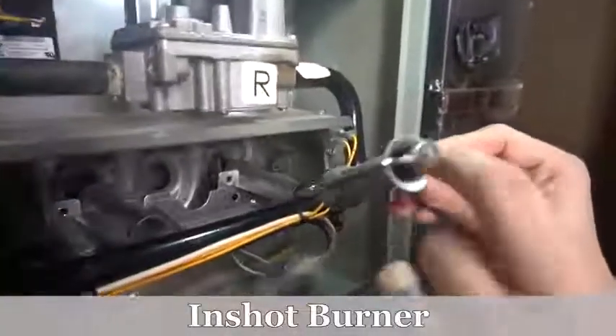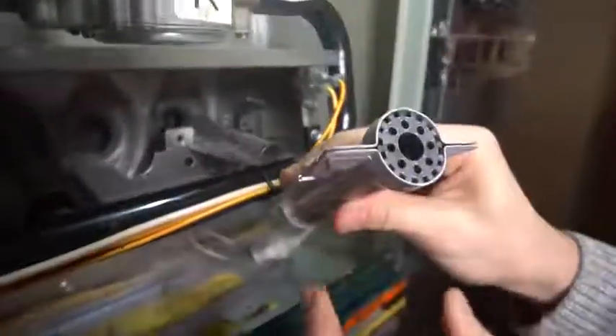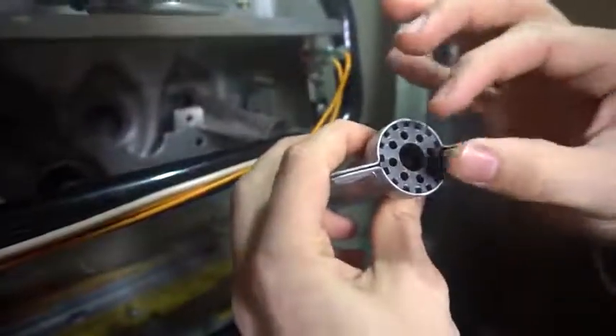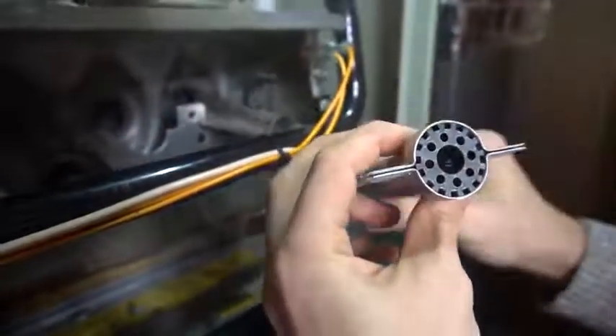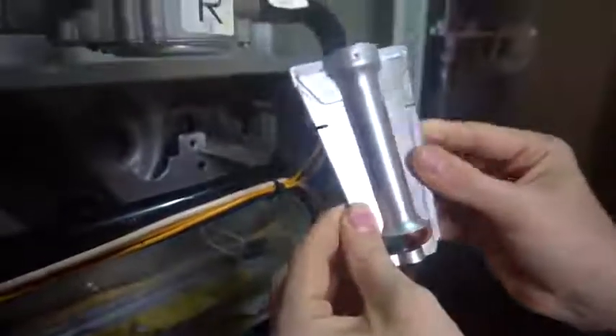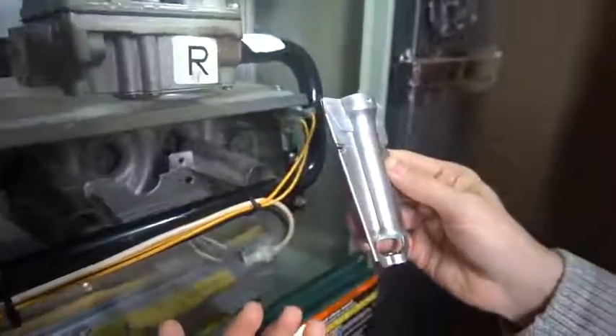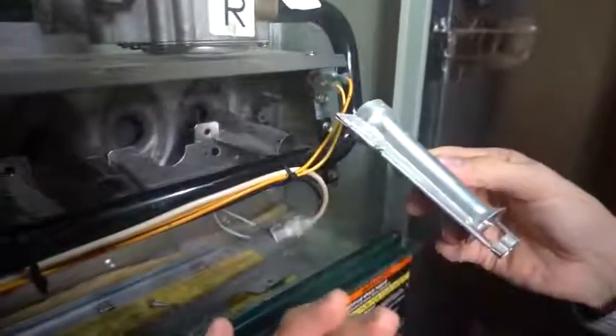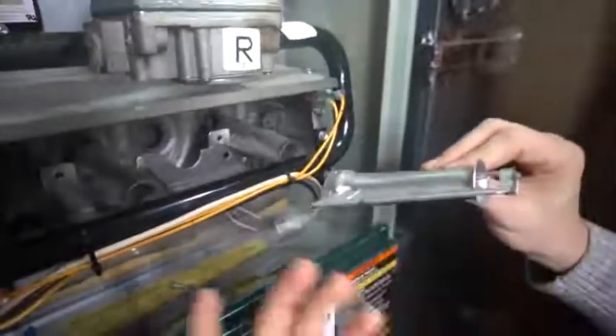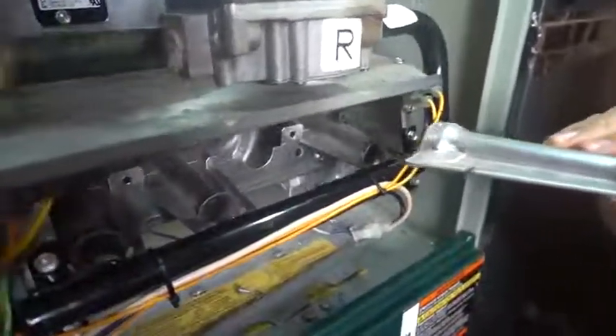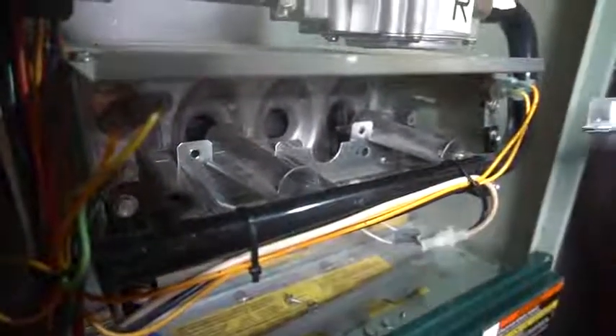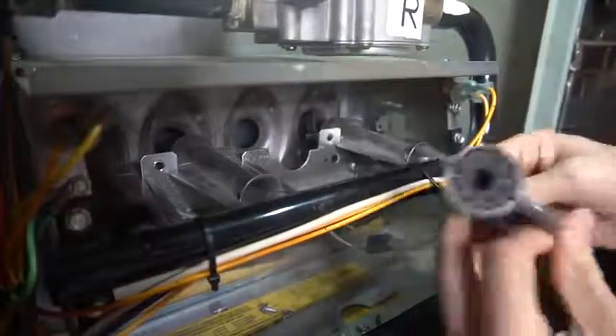So gas goes into here, and on the opposite side, you basically have a lot of holes, which disperses the flames and makes it into a cone shape. So this is what a burner looks like, and depending on the BTU rating of your furnace, that will decide how many burners you have. Generally, it'll be either 3 or 4 for most furnaces. If you have a big furnace or a lot of square feet, you might have like 5 or 6 burners. But anyways, this is what one would look like.